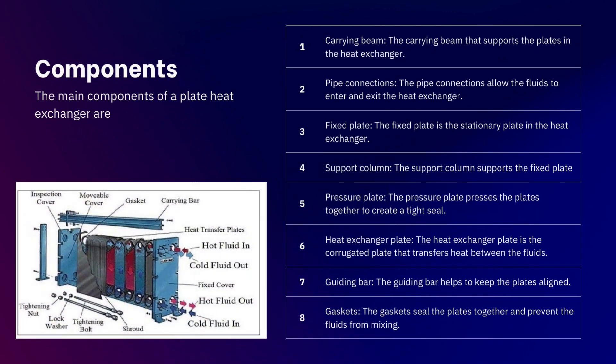The main components of a plate heat exchanger are: first, the carrying beam, which supports the plates. Second, pipe connections, which allow fluid to enter and exit the heat exchanger. There is a fixed plate, which is a stationary plate supported by a support column. The pressure plate presses the plates together to create a tight seal and prevent leakage or fluid mixing. The heat exchanger plate is the corrugated plate that transfers heat between fluids. A guiding bar keeps the plates aligned, and gaskets seal the plates together to prevent fluid mixing.